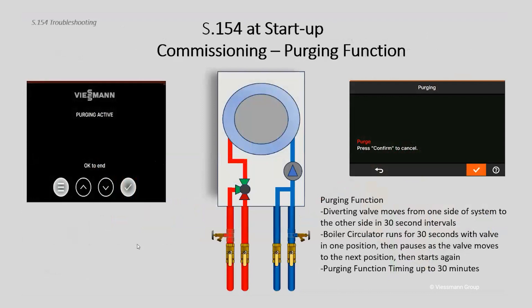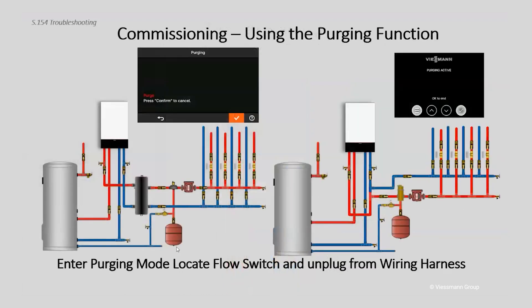If your expansion tank is at 15 PSI, about 18 PSI would be good for cold fill pressure. Eyeball the pressure gauge and toggle those boiler drains down until you get the right pressure, then shut the filling function off. Now we move to the purge function. In the purge function it's a 30-seconds-on, 30-seconds-off, 30-seconds-on interval. When you turn this on, the diverting valve moves to a position, the pump comes on for 30 seconds, then stops. The diverting valve moves to another position — you'll see it change on screen from the heating side to the domestic side — then the pump activates again.